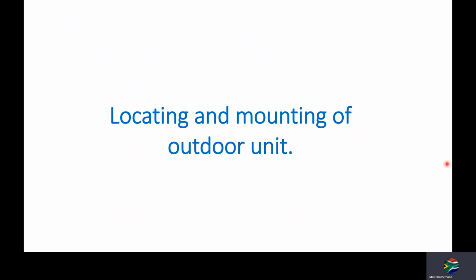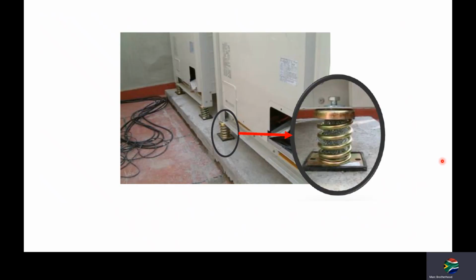Let's look at locating and mounting of the outdoor units. Here we can see outdoor units mounted on springs. This is not ideal for any DX systems. If it's a contained system like a chiller, it's different, but we strongly discourage mounting any VRV systems on springs because it's going to create stress on the copper pipework. The resonance, the oscillations, it's not good practice.